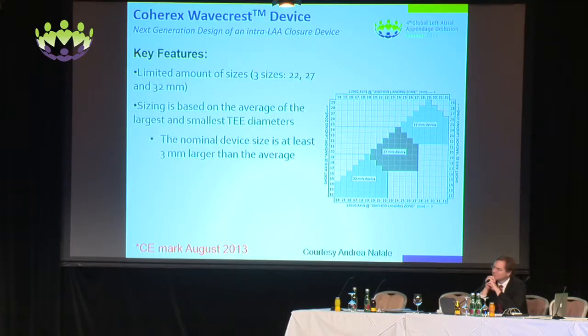The sizing is based on this chart. So you put your two numbers in that chart, and then you select your device based on that. Typically the nominal device size is at least 3 millimeters larger than the average that you found.